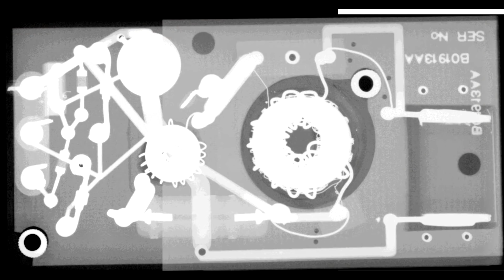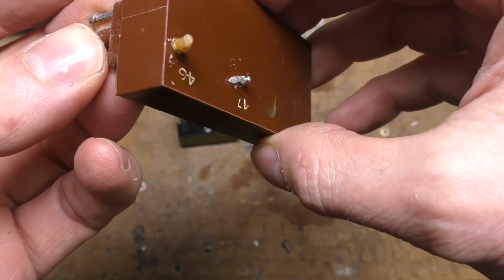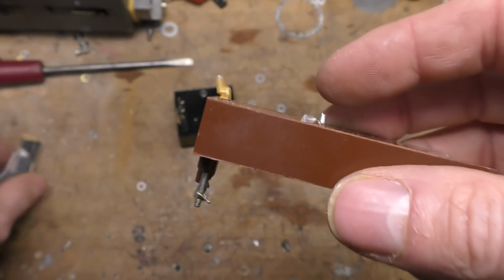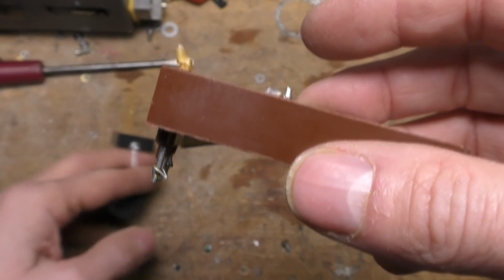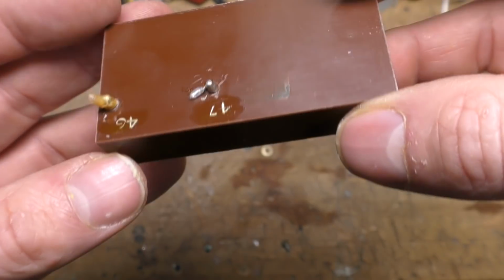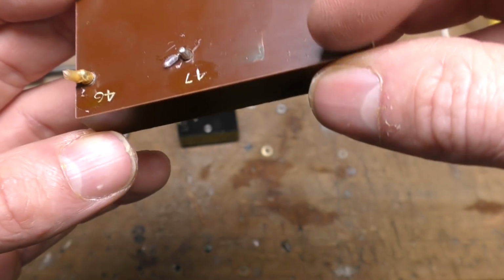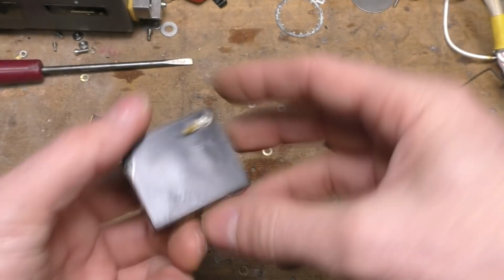This driver module, looking at the X-ray, looks like it has a couple of toroidal inductors and a transistor in there, so that's presumably producing some sort of voltage, maybe at a particular frequency. I know some of these devices work on fairly high frequency RF, but it's a bit hard to tell really what that's doing. And the trigger transformer, you can actually see the trigger coil on the X-ray, and also what I would presume is a thyristor and a capacitor to produce a high voltage pulse to strike the tube.